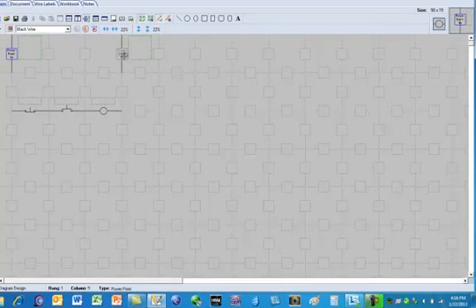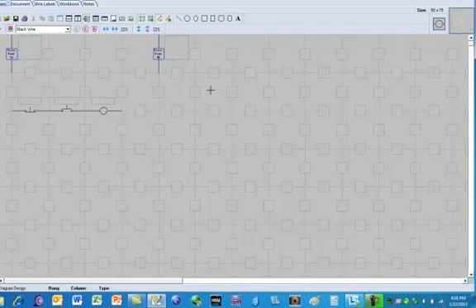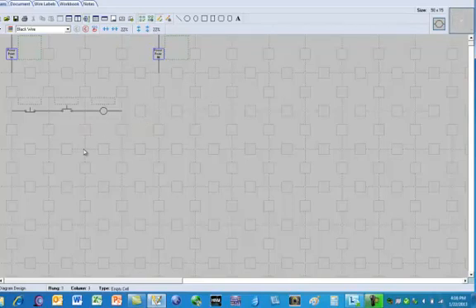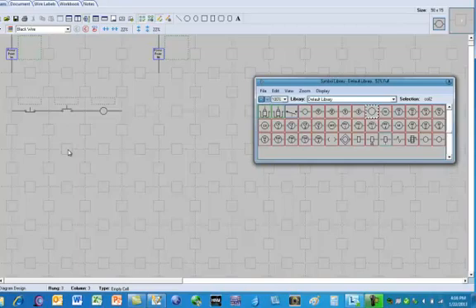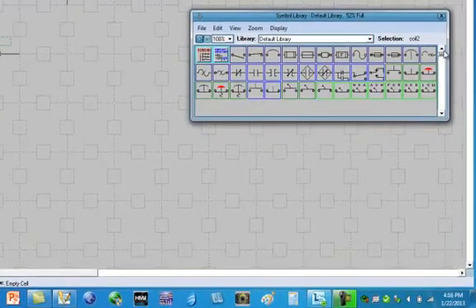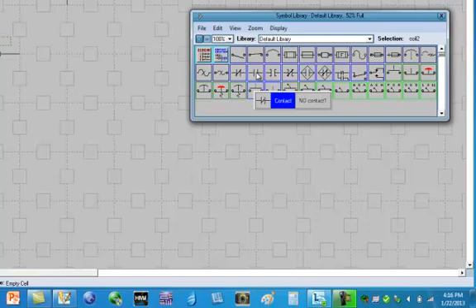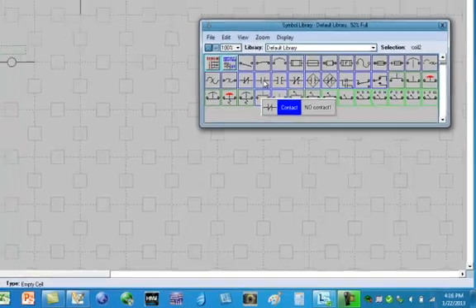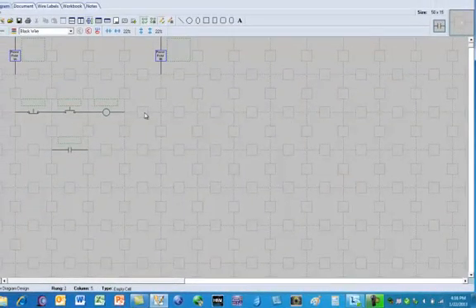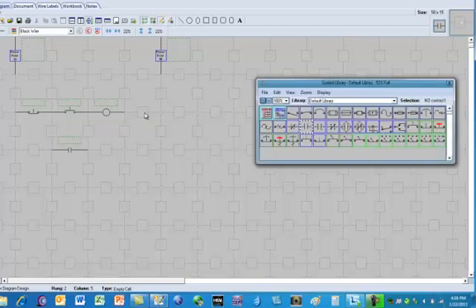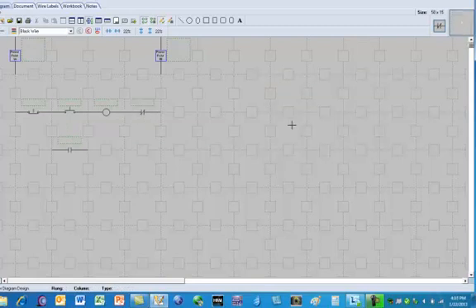I'm going to slide this over one more spot because we still need to install our overload contact here and our holding or memory contact below the start button. So I'm going to put the normally open contact in there first. Again, normally open contact. I'm going to put my normally closed over here that I use for my overloads. So now I have all the basic components clicked and installed on the desktop.